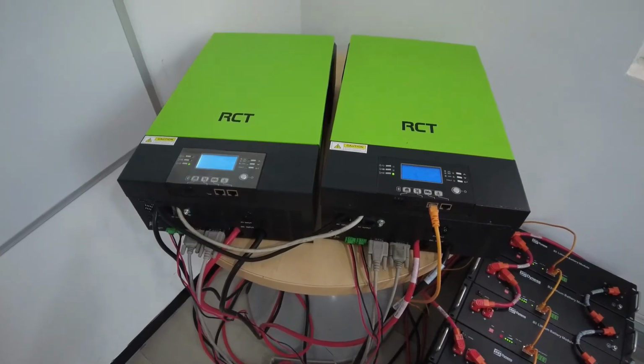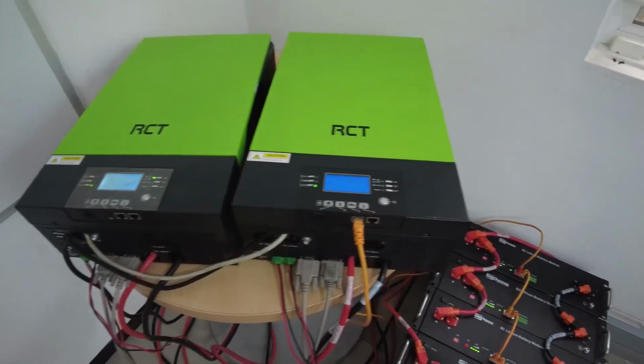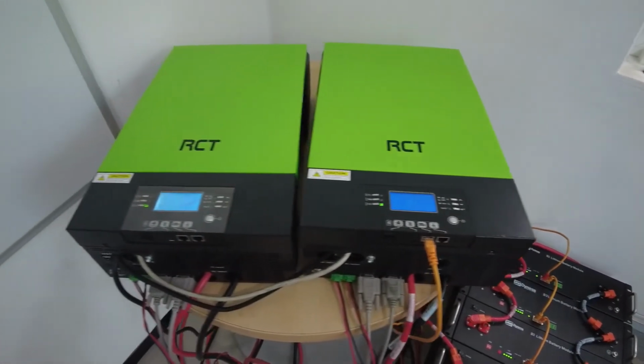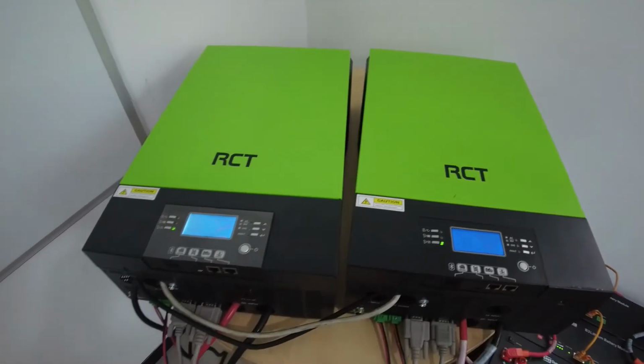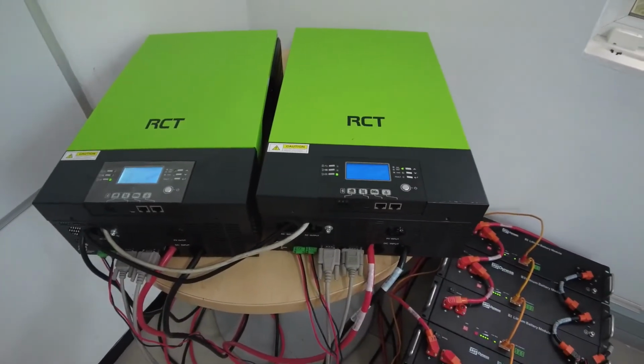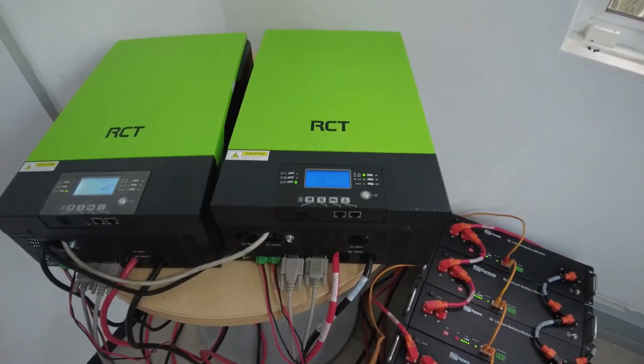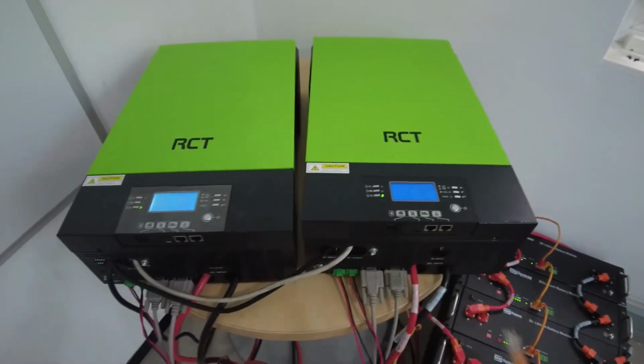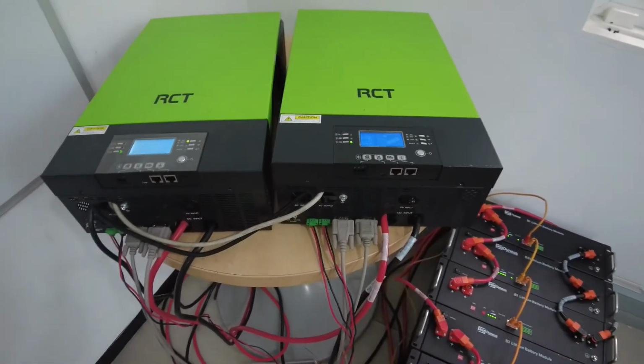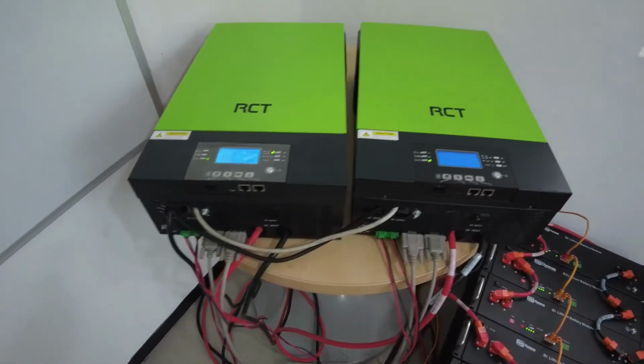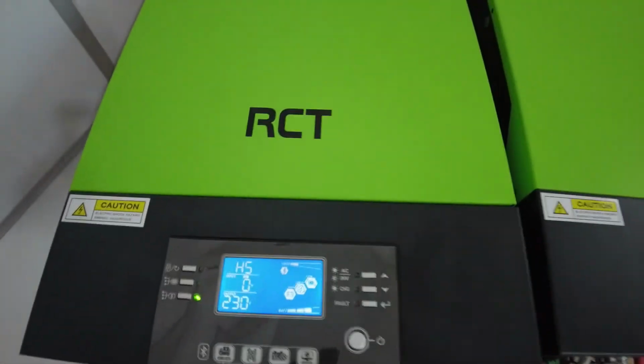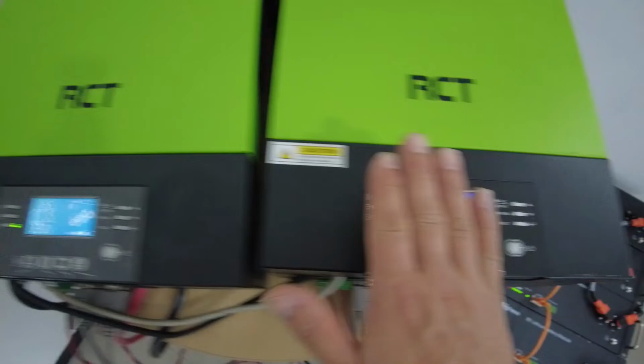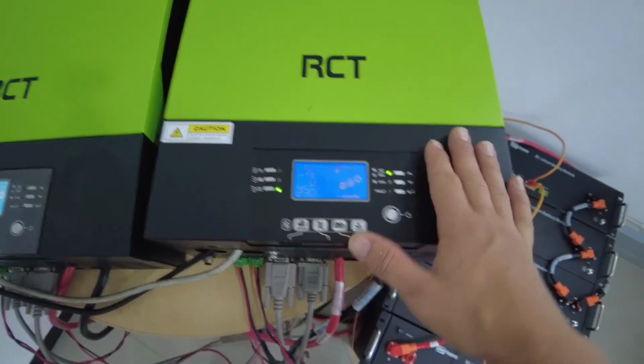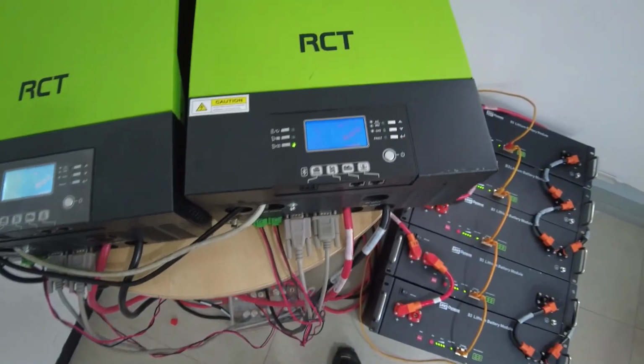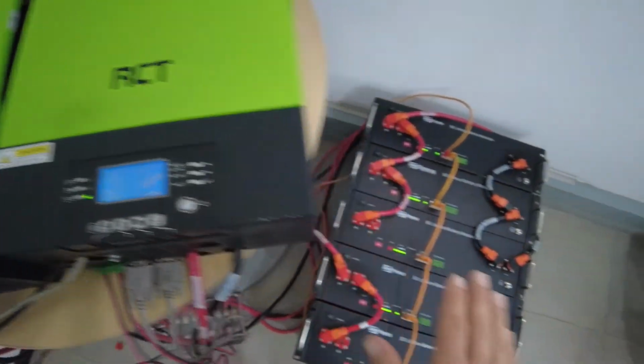Okay, so next up is the BMS communication, to get the inverters set up to communicate with the batteries on BMS communication. Note I've just unplugged this cable. I actually want to see the inverter not communicating with the batteries. Now, as I've mentioned before, it does not matter which one of these inverters is master and which one is slave. The one connected to that BMS cable will be the inverter communicating with the batteries.